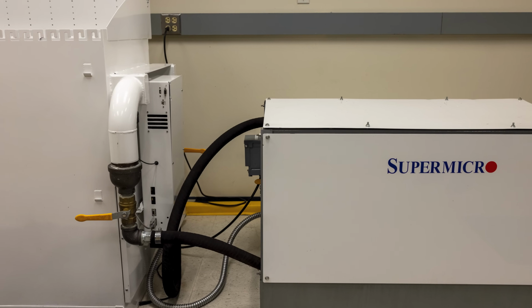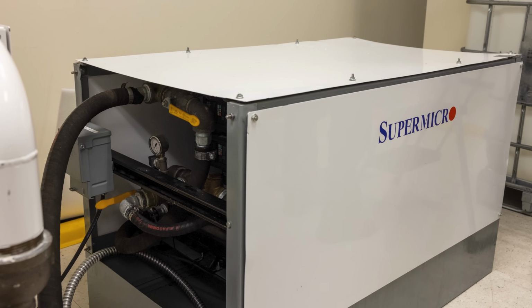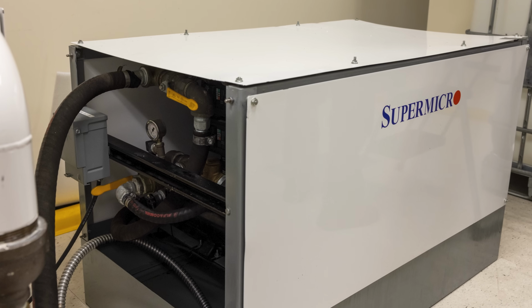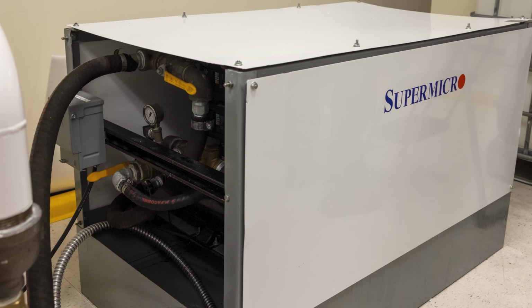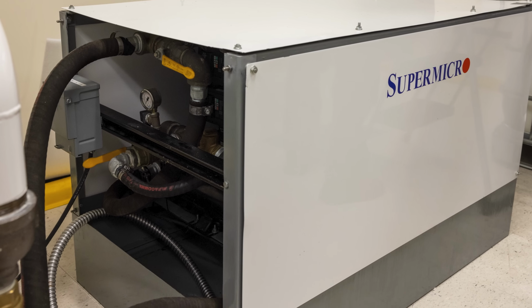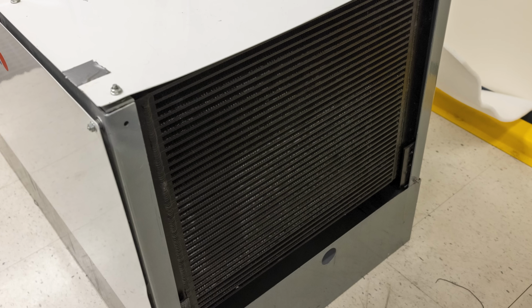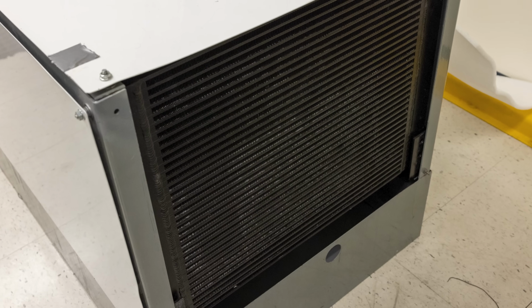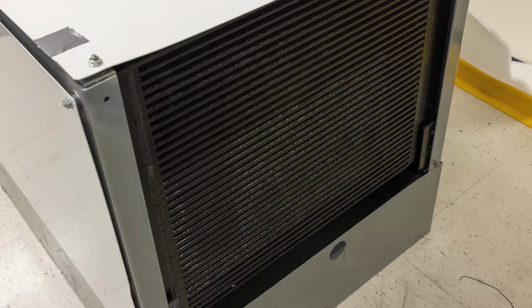So what you actually see is that often you'll have a heat exchanger that sits outside of the tank, and that heat exchanger basically will take the non-conductive liquid that's heated up and pass it through the heat exchanger, will go to facility water, and the facility water will take the heat and bring that out of the, I guess, data center floor. And this solution is actually becoming quite popular because there are a number of benefits.